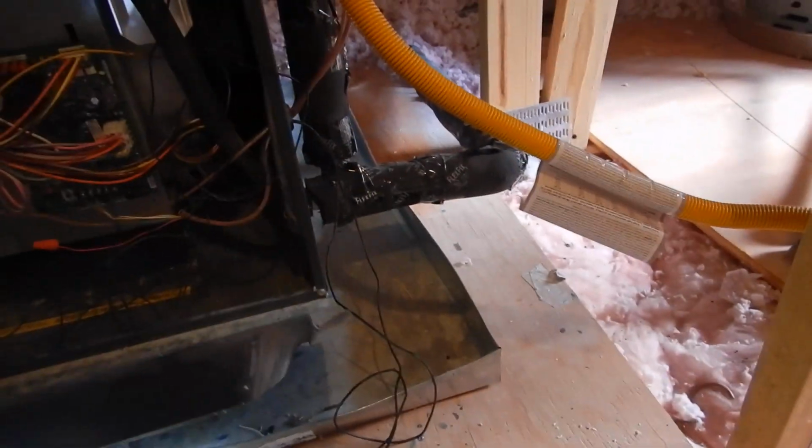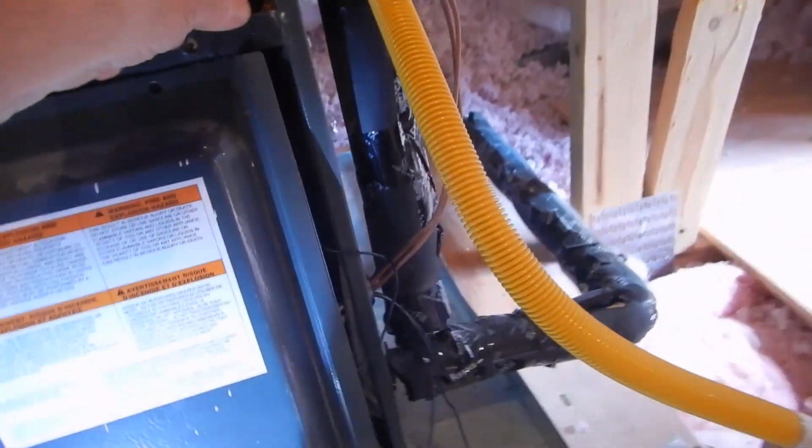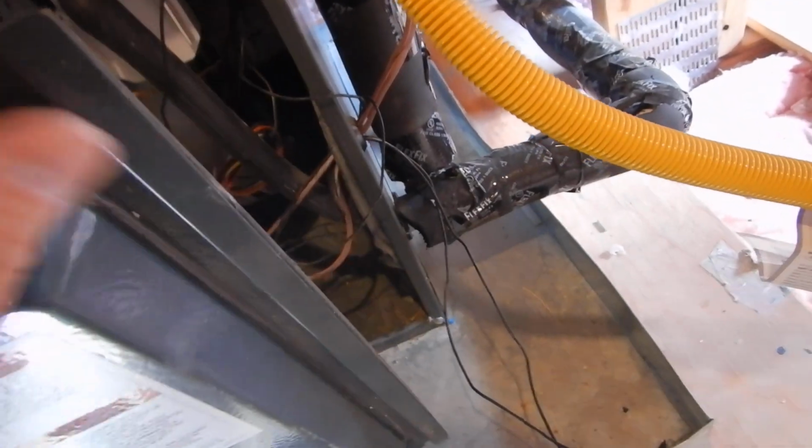Furnace is really nothing to talk about except for the tape, except for the exposed gas piping, except for the control manual not being there, and the rust inside the burner compartment. So we want to know what that's about. We do not have a neutralizing filter. We don't think we have a neutralizing filter. This wire just hanging out here. It's kind of weird how they did that. They just decided to put the wire like that. Come on, we can be more fastidious than that.